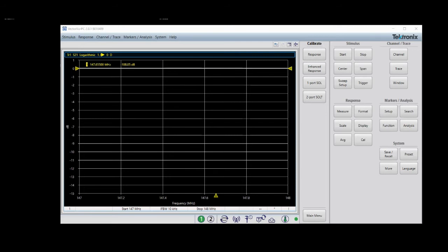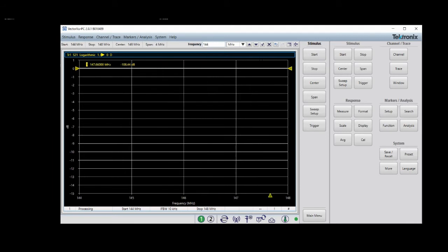We're all ready to go to do our calibration and measurement of the gain of the RF preamplifier. First thing we want to do is set our start and stop frequencies. So 144 M for meg, and stop, it's already set to 148. Now remember, we need to also change the stimulus power. So we're going to go to Sweep Setup and Power menu, and here power level is right here. So we're going to change our power level to minus 35 dBm. So now our stimulus level is set where we want it. No need to use an attenuator.